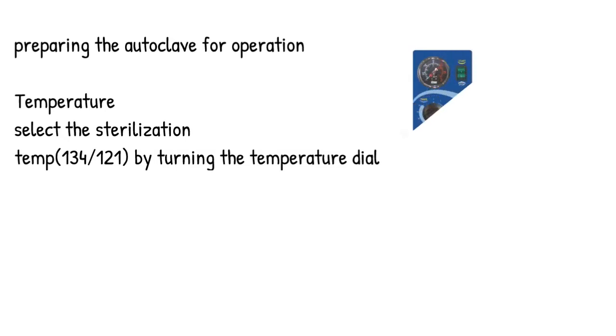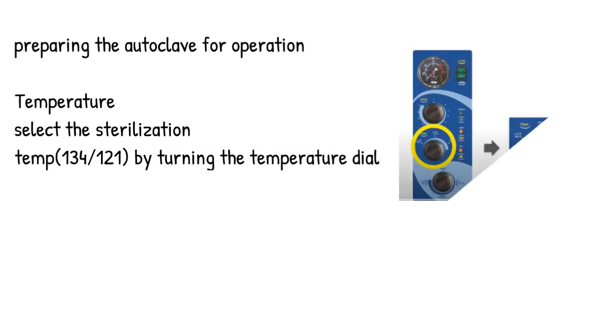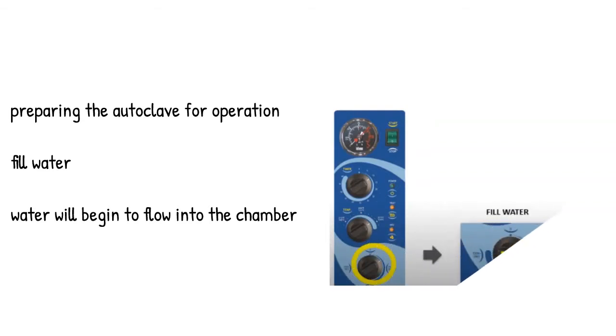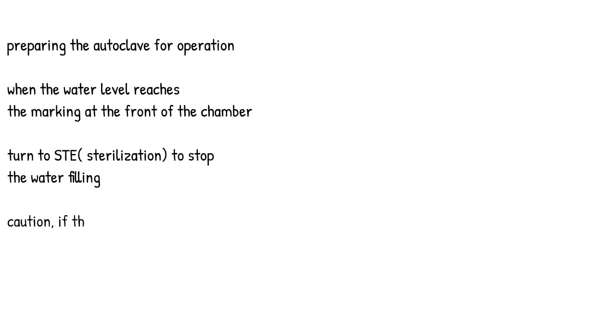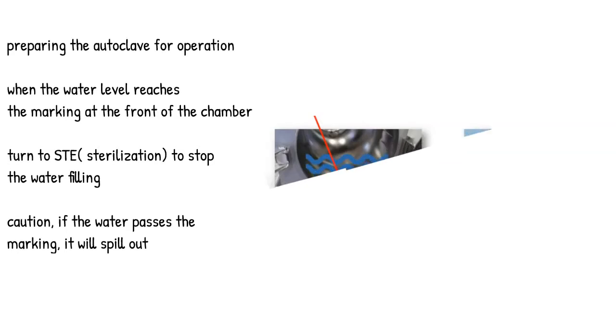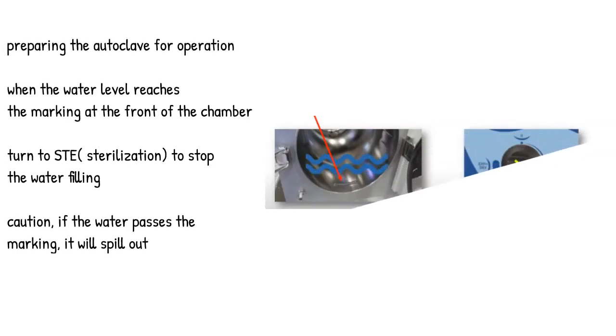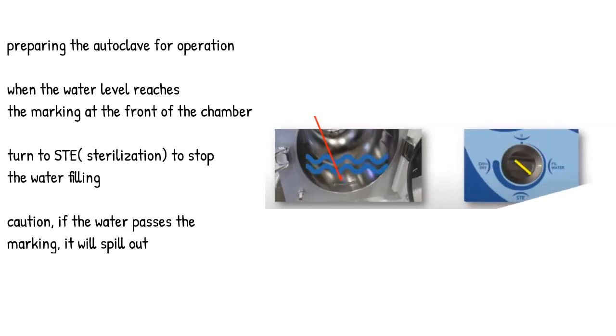Temperature: select the sterilization temperature, 134 or 121, by turning the temperature dial. Preparing the autoclave for operation. Fill water. Water will begin to flow into the chamber. When the water level reaches the marking at the front of the chamber, turn to STE, sterilization, to stop the water filling. Caution: if the water passes the marking, it will spill out.